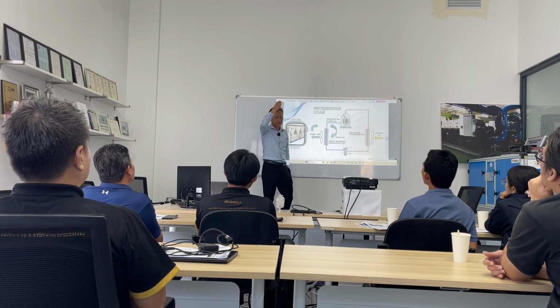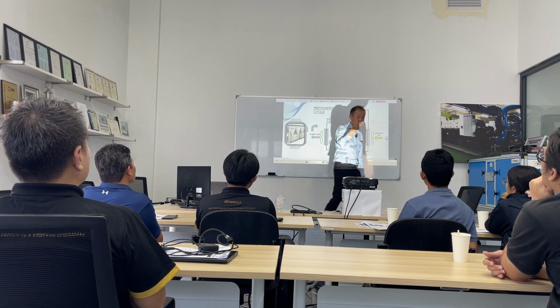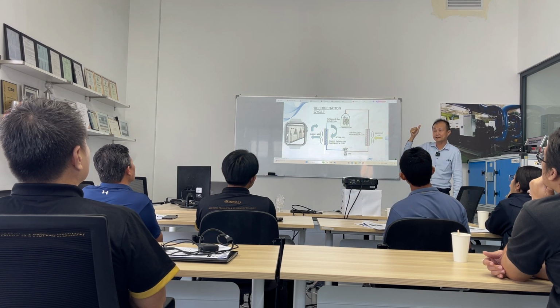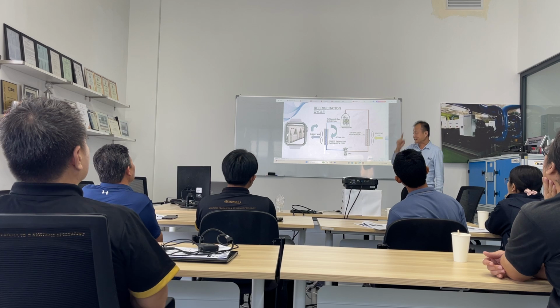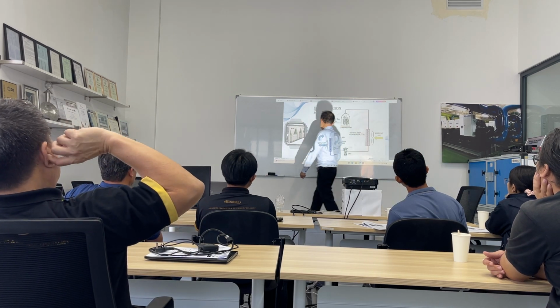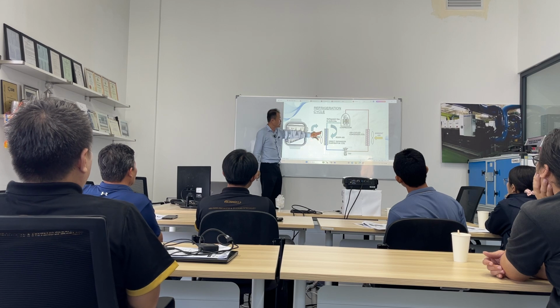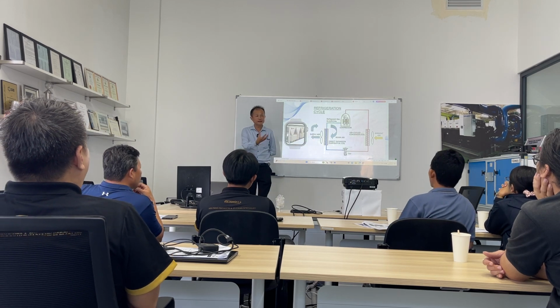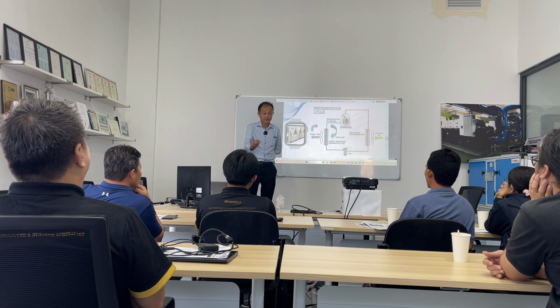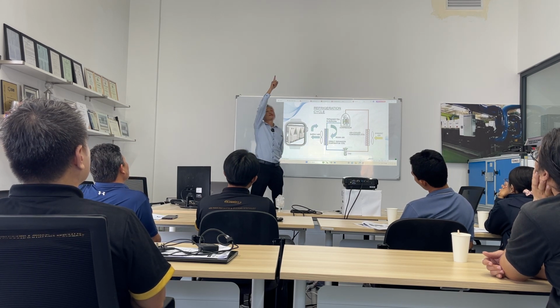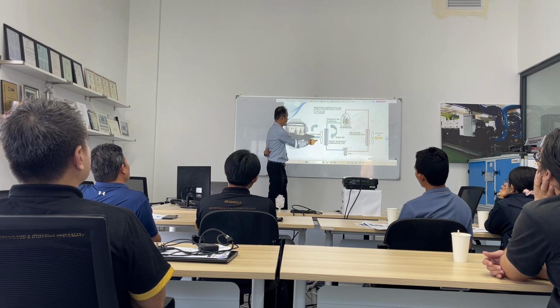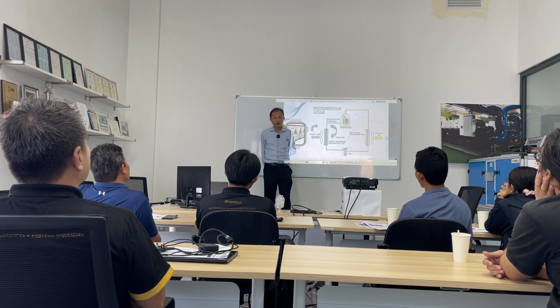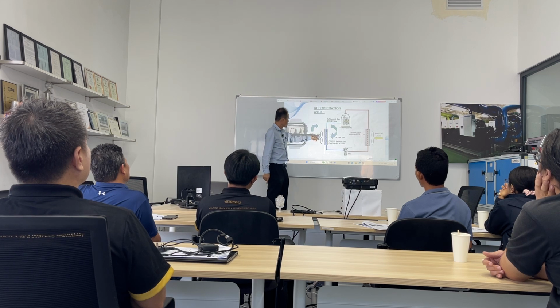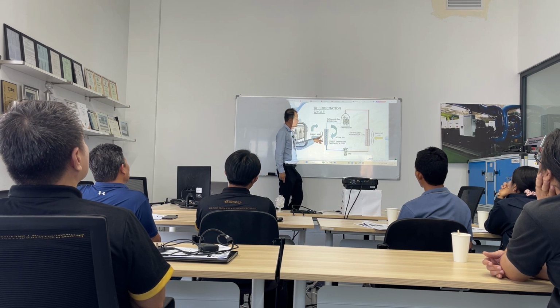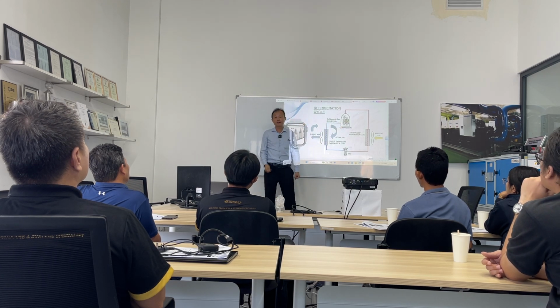So when you use the remote control to start the system, the first component that will run, of course, is the blower. The blower sucks the air from the space here, into the cassette unit, and then through the evaporator coil. At the same time, there is a control wire to tell the compressor to start running.